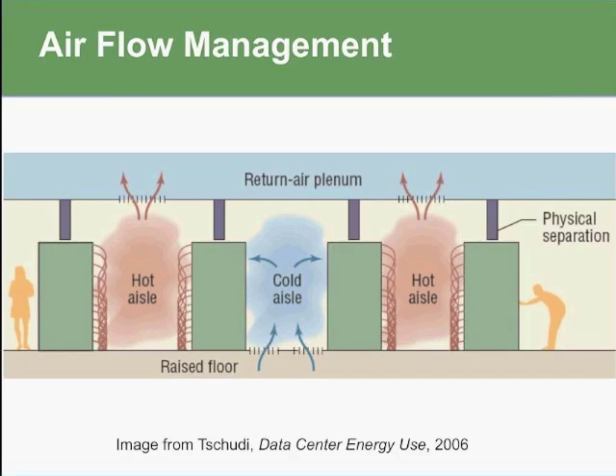So this graphic just beautifully lays out a perfect airflow where you have cool air coming into the cold aisle section and going into the front end of your servers, assuming that they're oriented correctly, cooling the servers, and then the hot air is being immediately sucked out into the return air plenum such that the servers only see cold air, and the hot air is not mixing with the cold air, which obviously is inefficient and provides higher cooling temperatures to your servers, which is also very inefficient.